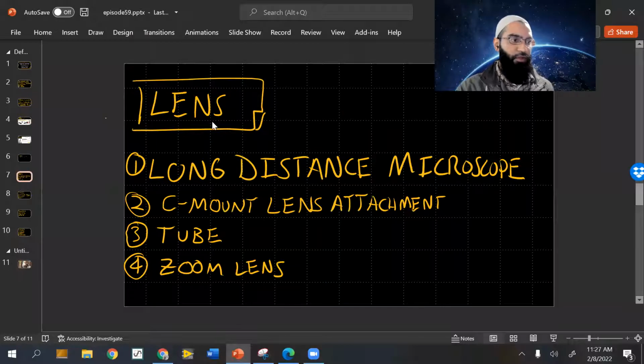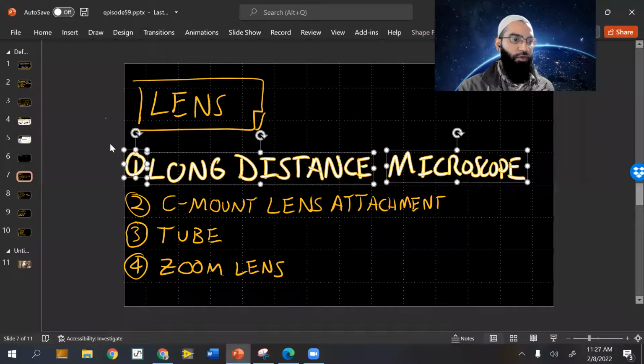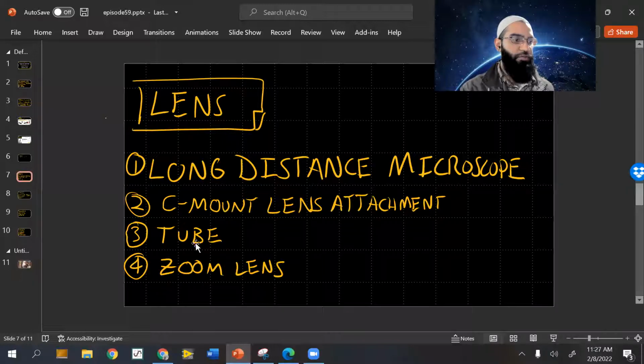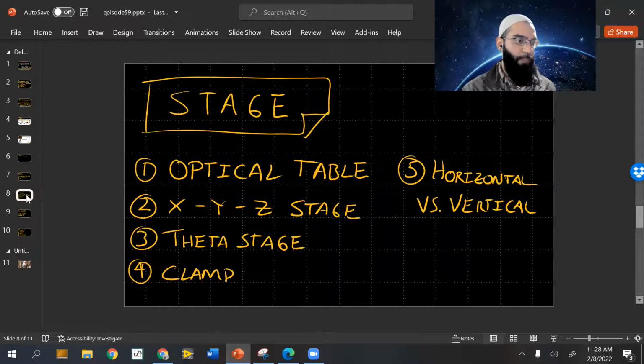So we talked about the lens a little bit. You're going to be using a long distance microscope system. There'll be a C-mount attachment, a tube, which is going to get you the larger focus range, which in my case is about 5 to 6 inches away from your camera, so that just worked out really great. And obviously with the zoom lens, you'll zoom out in order to get your device in the screen, and then you'll zoom in and adjust the height of the camera in order to properly bring your transducer in focus.